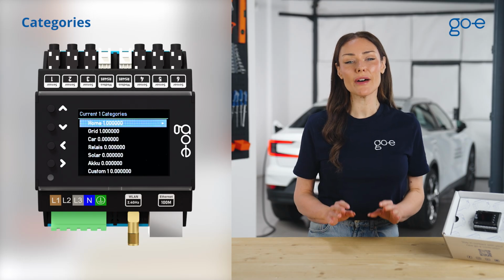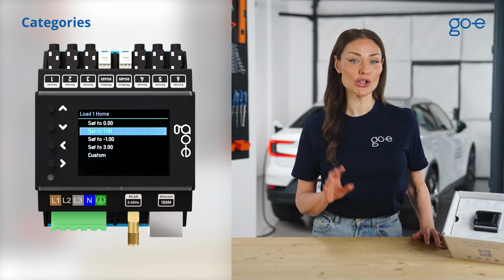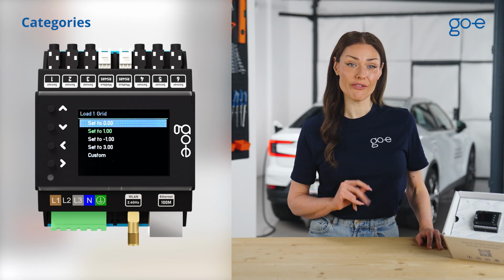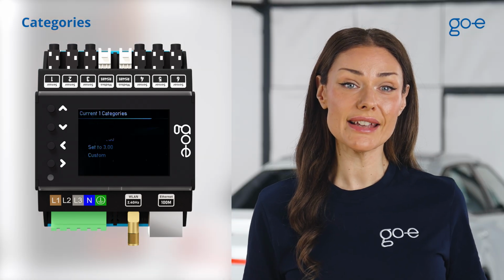After identifying the correct categories, you can set them in the menu. In the submenu, define which sensor value should be assigned to which category and with what factor. For a 3-phase grid connection, assign the same input values to current 2 and current 3 as you did to current 1. The next steps I'll show you are optional.